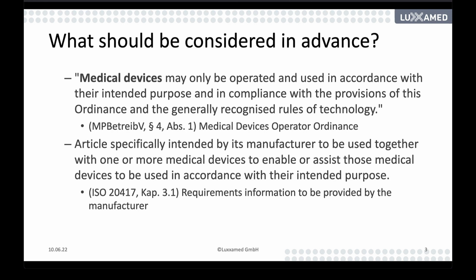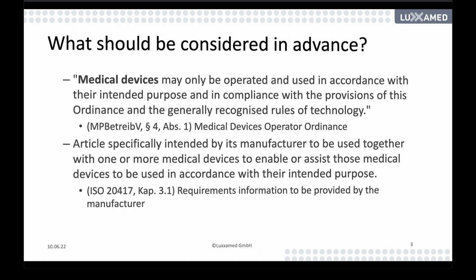When a manufacturer says that this part and this part are needed to work with this medical device, then there are some ISO norms about the requirements of information to be provided by the manufacturer. Please look in the instructions for use at what the manufacturer describes about it. By the way, all parts you need to work with your microcurrent medical device have to be listed in the instructions for use. If they are not included there, it may not be allowed to use them.